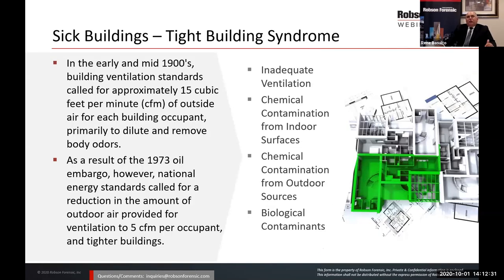All right, so what are sick buildings, or sick building syndrome, or tight building syndrome? It goes by several names. And how do we get there? In the early 1900s, ventilation standards were established when buildings started to be enclosed a little bit more. During that time, several organizations established that about 15 cubic feet per minute of outside air, fresh air coming in from the outside, per occupant of the building should be introduced to the buildings. And that was primarily to dilute and remove body odors.